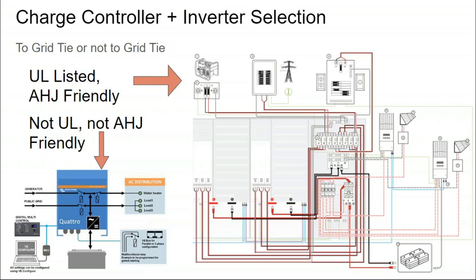That can come down to a sizing issue. If the solar array is sized substantially larger than the generator, it could overpower the generator and cause it to stop working.